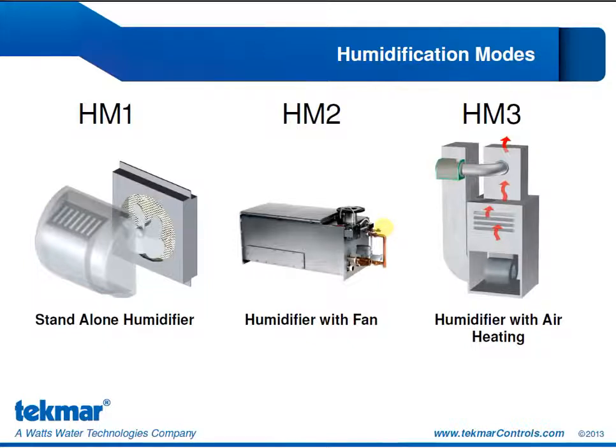Humidification mode 2 is a humidifier that requires a fan. So this type of humidifier can provide humidity without using the heat from your system, but it does need the system blower to move the water vapor through the building. An example of this is a steam injection humidifier, where water is boiled and injected into the duct, and then carried throughout the building through the ductwork by the system blower. So this humidification mode can be operated year-long because we don't need to use or rely on the air heating from our HVAC system.